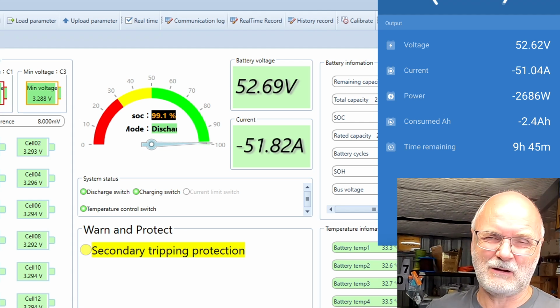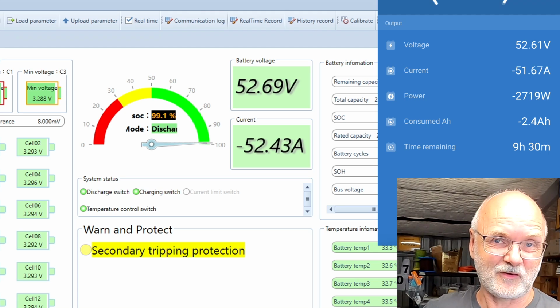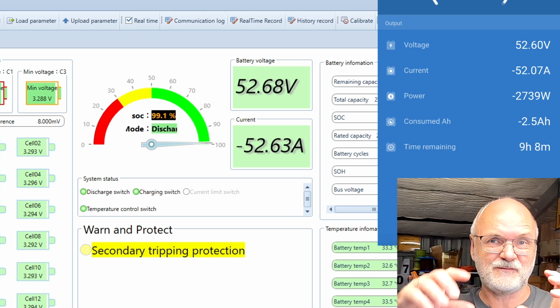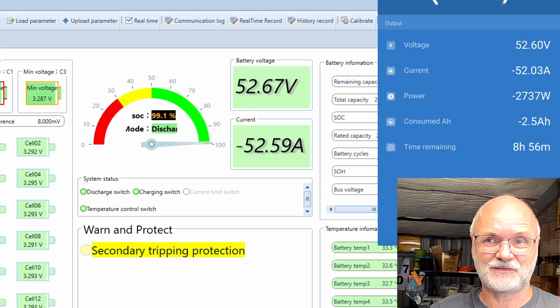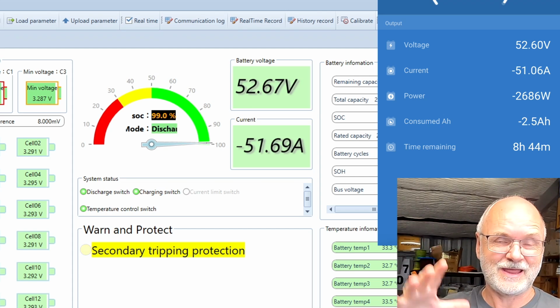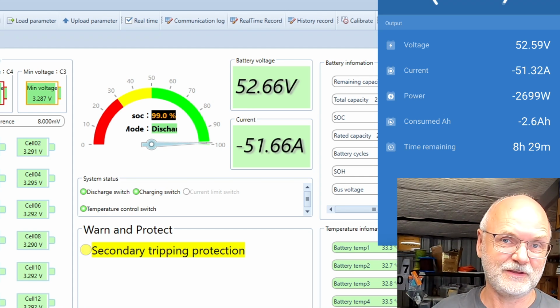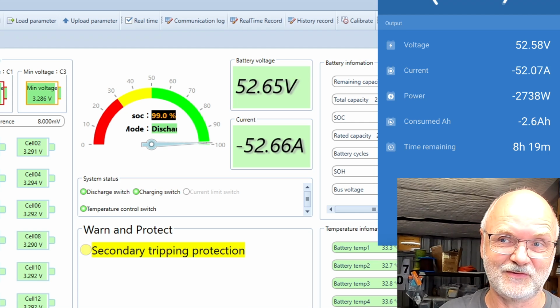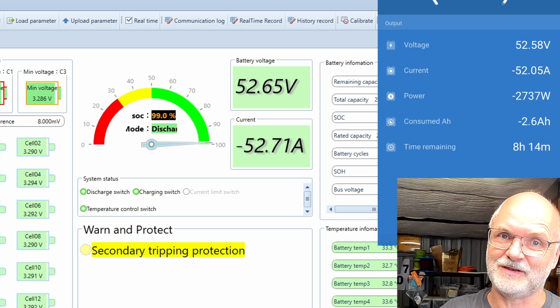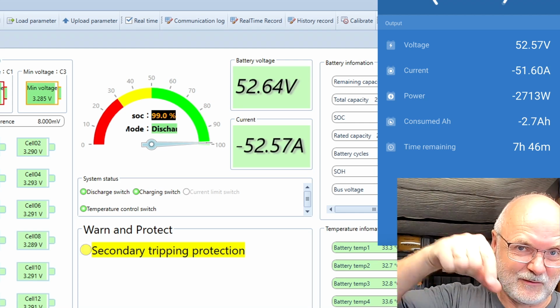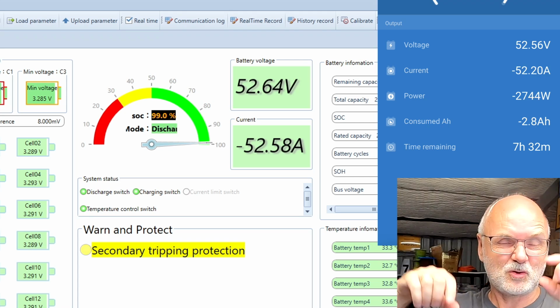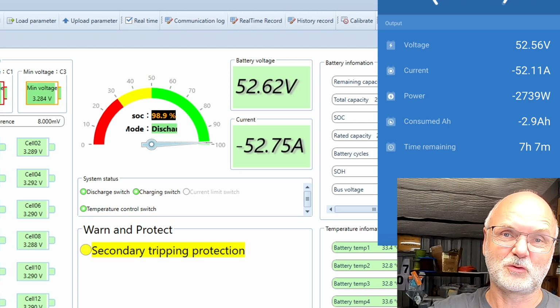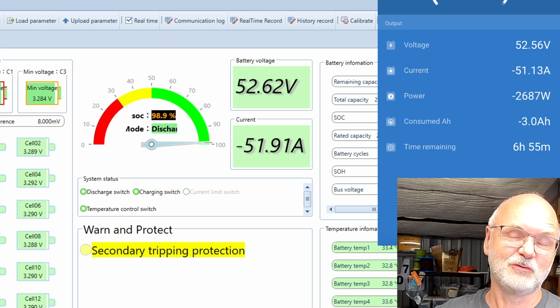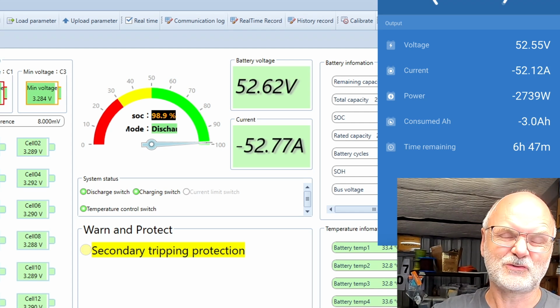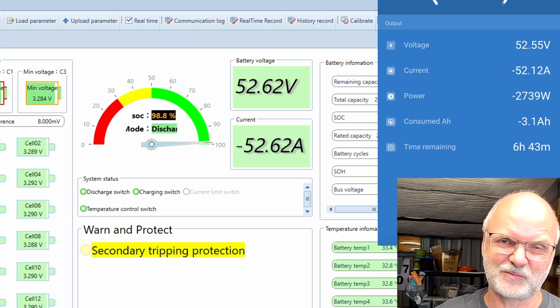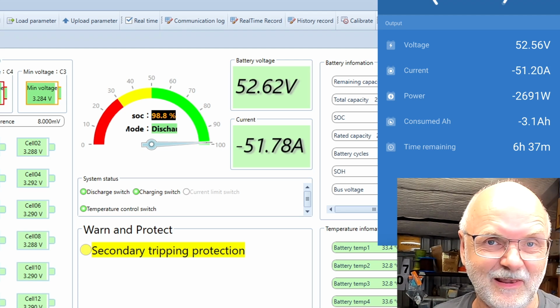After an hour, 2 hours, 3 hours or so, I will have a look with the infrared camera as well on the whole battery, to see if there are any hotspots in the cabling or something. Because this is a brand new build battery, we have to check all these things just for safety purposes. As you've seen, you easily miss one of the nuts, even on top of the BMS where all the flexible bus bars are now. There could be one screw which I've missed. So it's always a good idea to check this all twice and use the infrared camera if you have one, just to see if there's any heat building up, any hotspots or something. If you haven't got one, I'll link one down below.